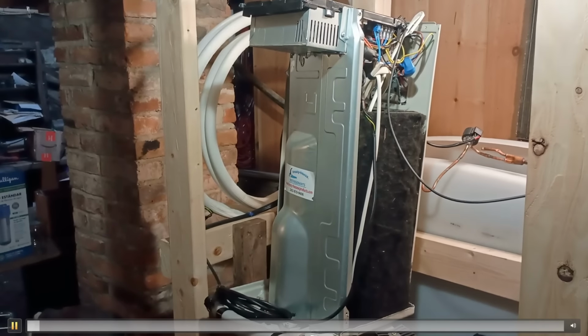Now, as the temperature outside decreases, the amount of heat it can output decreases. So if you go down to 10 degrees Fahrenheit, now you're at like 13,000 BTUs, so like a 30-something% drop. You go down to 0 degrees, now it's only putting out about 10,000 BTUs, almost half, almost cut in half what the output of that system is.